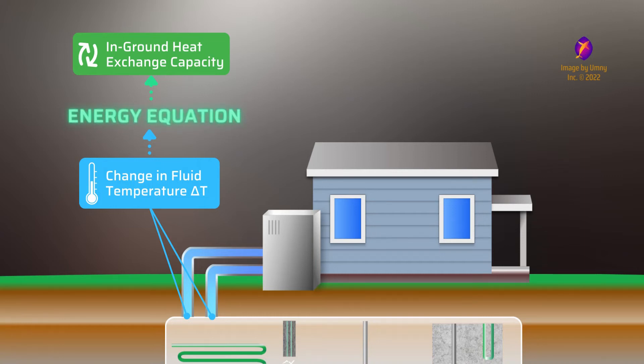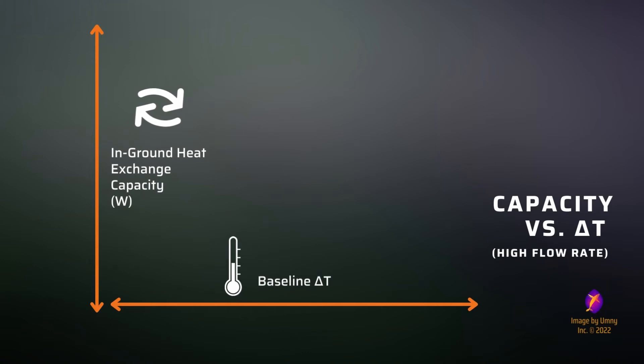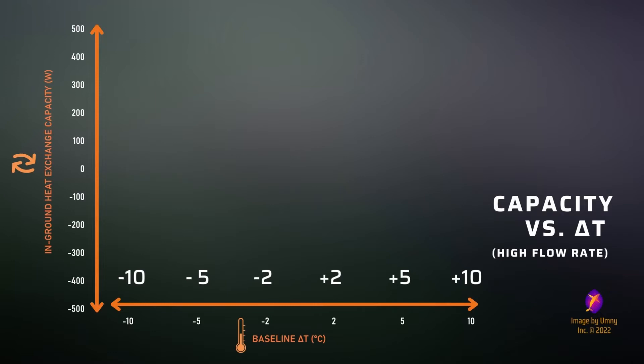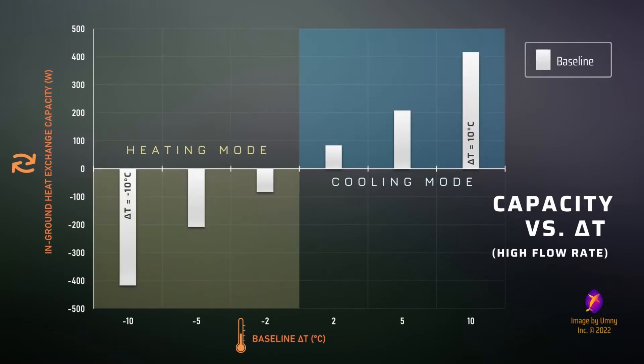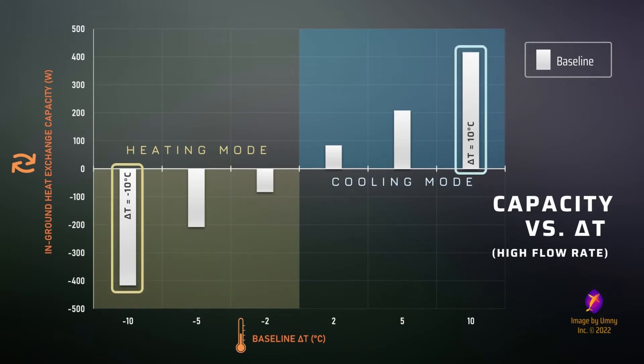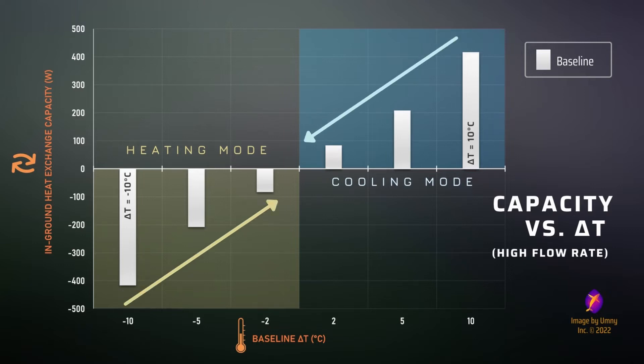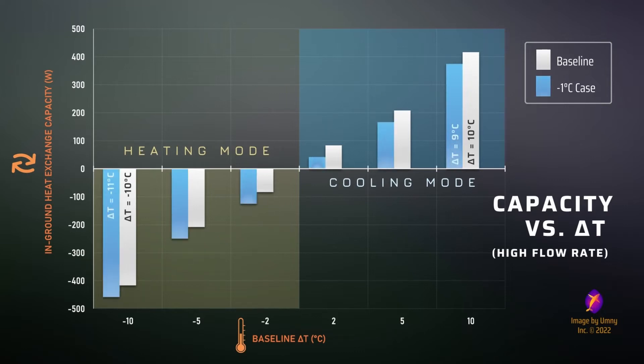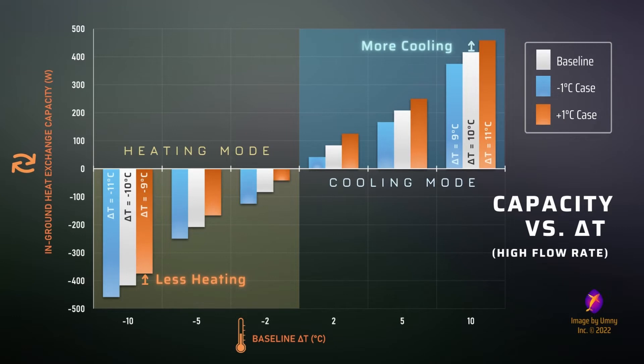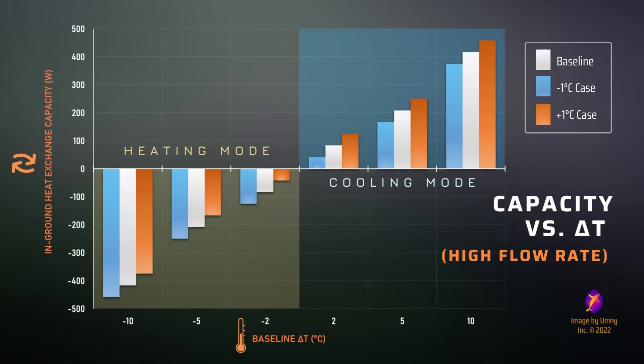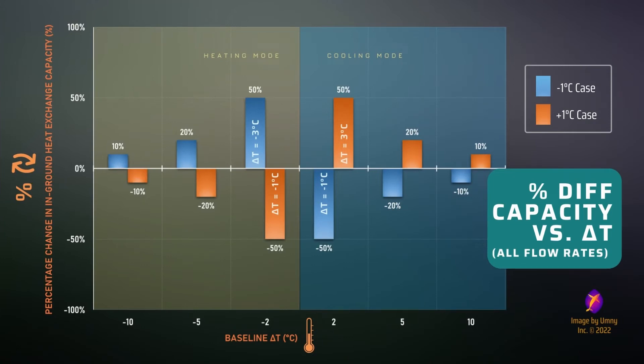Using the energy equation with a constant flow rate and fluid properties, we can compare the baseline delta T to the in-ground heat exchange capacity that results. Here we're working with three delta T magnitudes of 2, 5, and 10. For our baseline case, we expect the heating and cooling capacity from the in-ground heat exchangers to be just over 400 watts when the delta T is minus 10 and positive 10 degrees Celsius respectively. As the change in fluid temperature reduces, the in-ground heat exchange capacity decreases. If the baseline delta T were reduced by 1 degree for all cases — from negative 10 to negative 11 degrees Celsius — this results in more heating energy than the baseline case and less cooling energy. When the baseline delta T is instead increased by 1 degree Celsius, the in-ground heat exchangers produce less heating energy in the heating mode but more cooling energy in the cooling mode. The magnitude of all these values is affected by the fluid's flow rate; however, the percentage difference in capacity from a 1 degree Celsius change is the same for all flow cases.